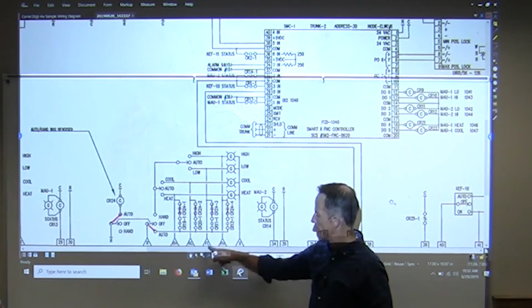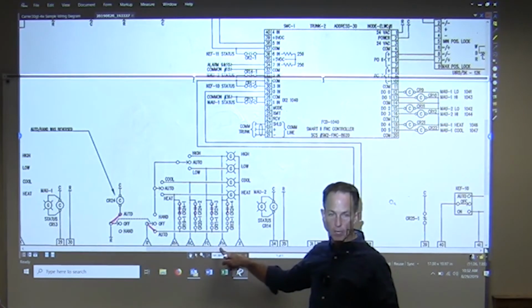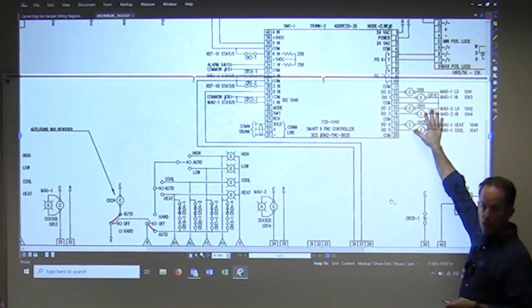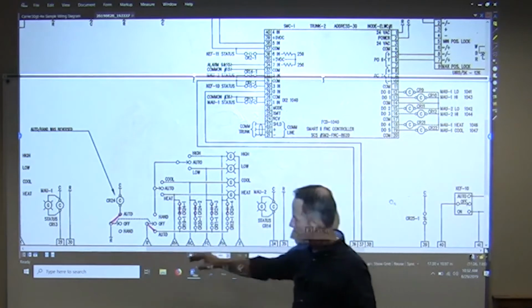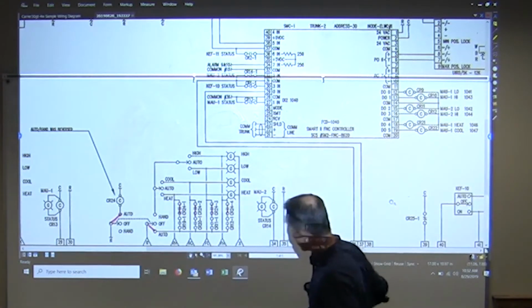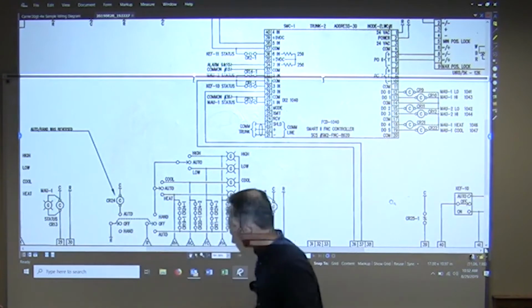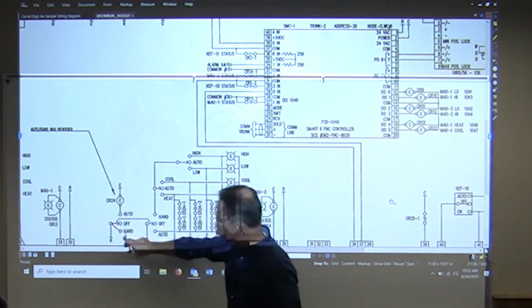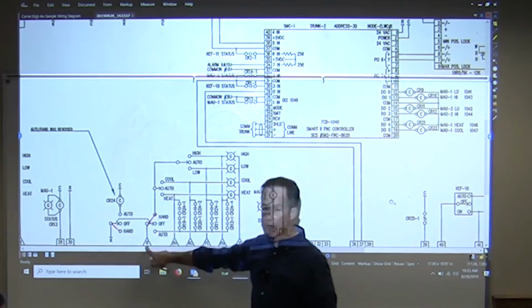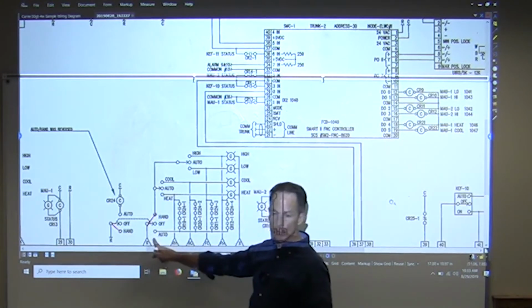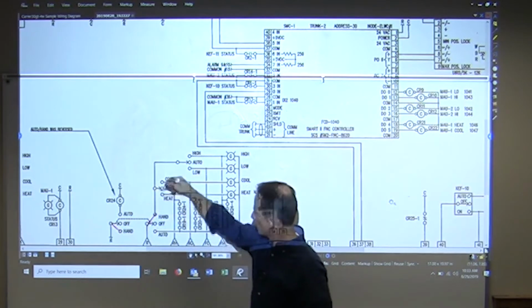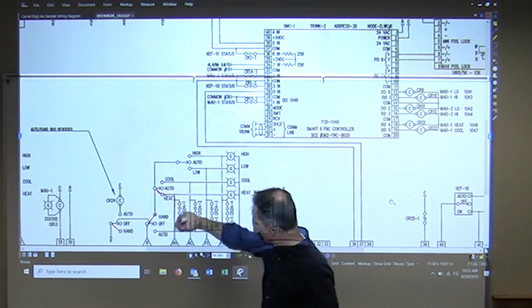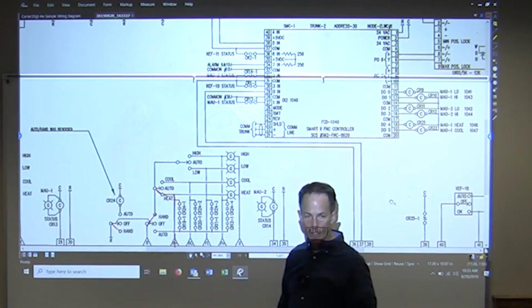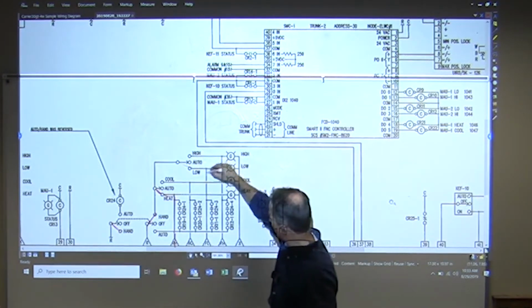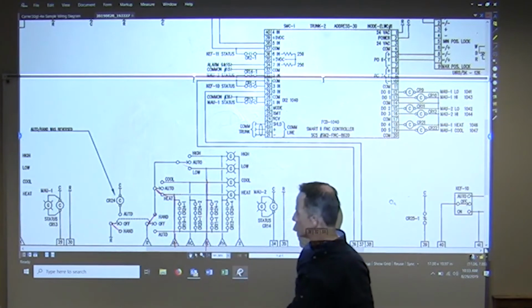What about 11 and 12? It's your low and high speeds, right? And again, those are controlled through the automation system or in automatic. If I were to switch things to hand, those open back up. Hand doesn't do anything here, right? It goes to dead, but this then takes my R from the unit, so it's R's coming from the unit, goes up to the switch, and so if I say heat here, and it just comes straight back down, and I've got heat on there. Or if I go here, I go low speed right out there. Okay.